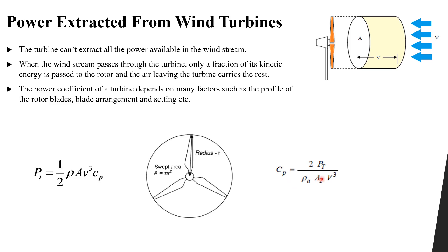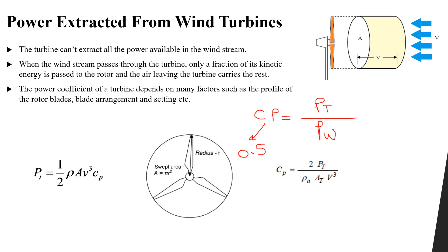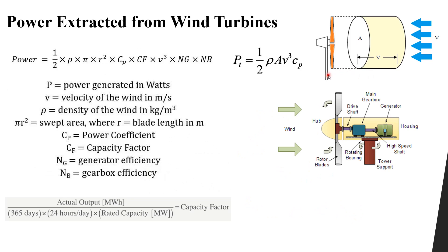Cp, which is the efficiency, is equal to the power absorbed by the turbine divided by the power available in wind. For example, if we have a power coefficient Cp of 0.5, it means the power absorbed by the turbine is equal to 0.5 of the power available in wind — so our turbine took 50% of the wind energy.